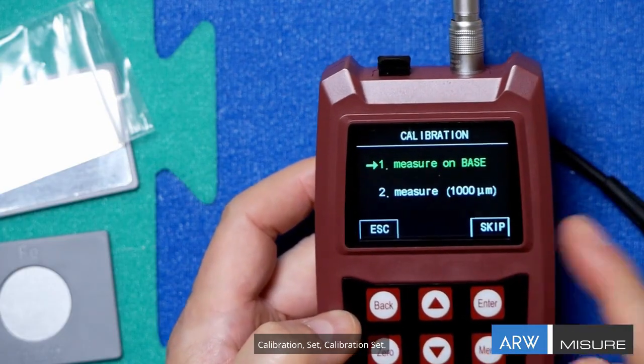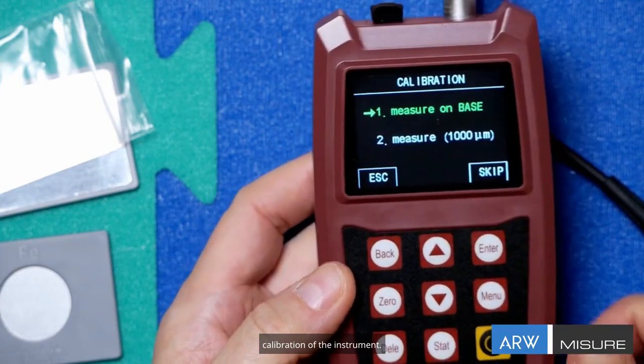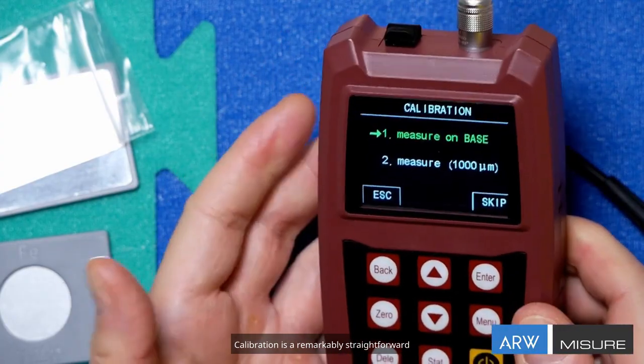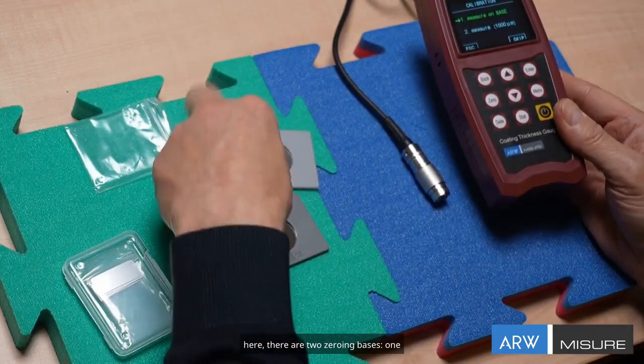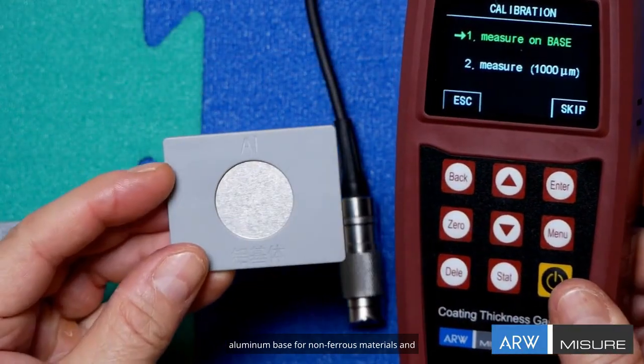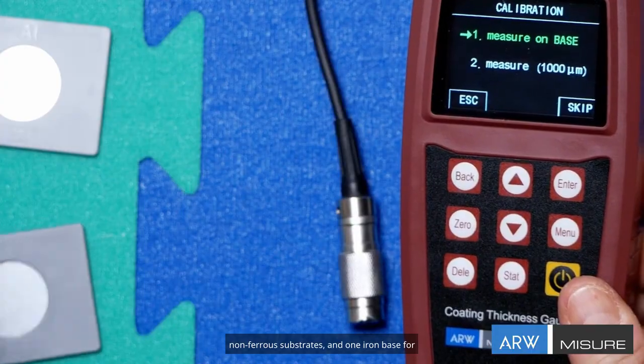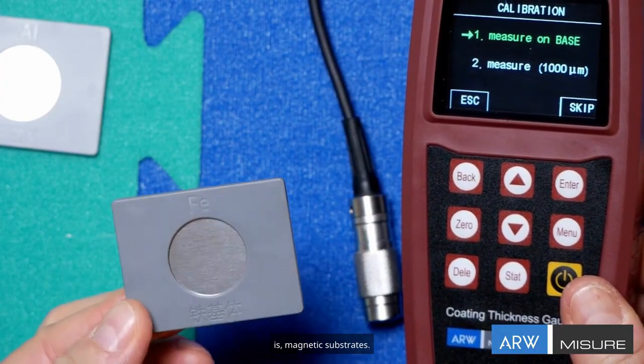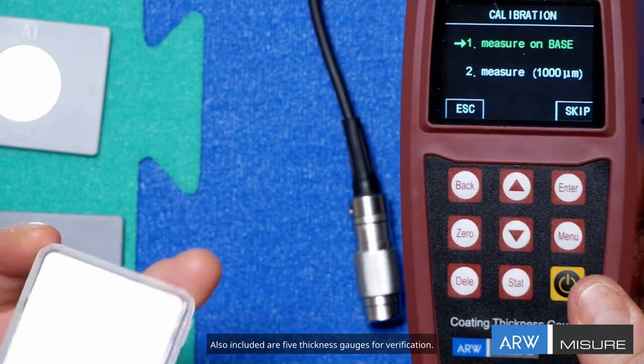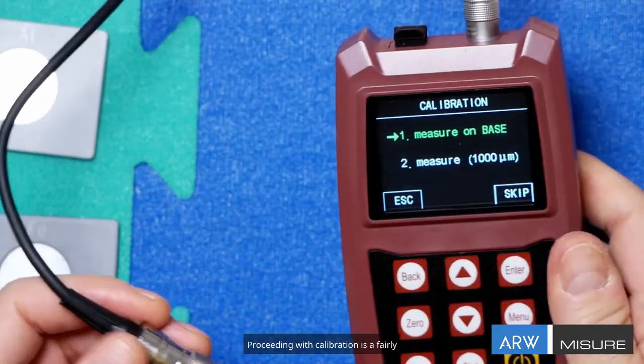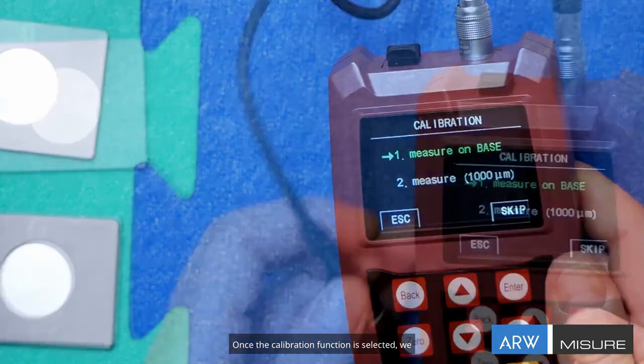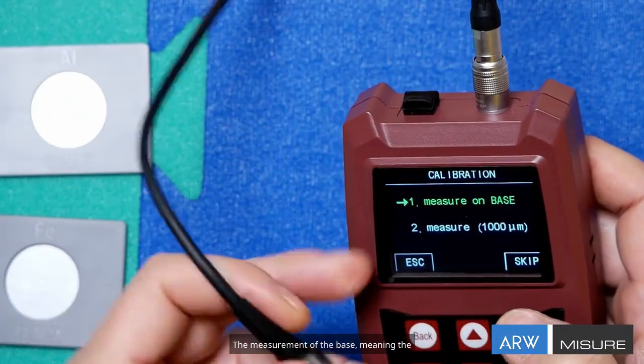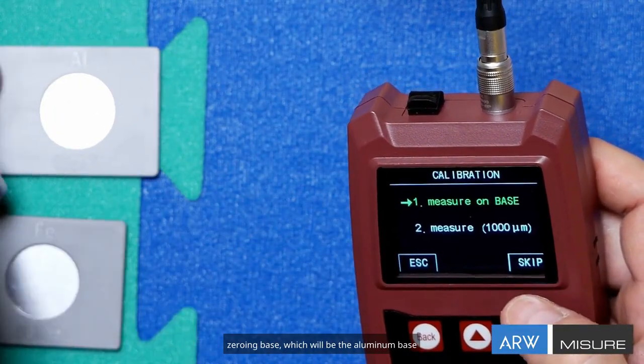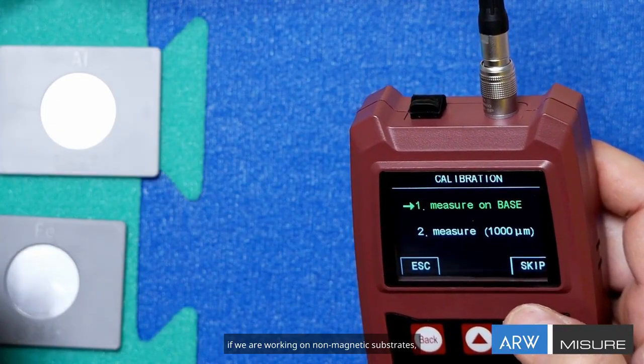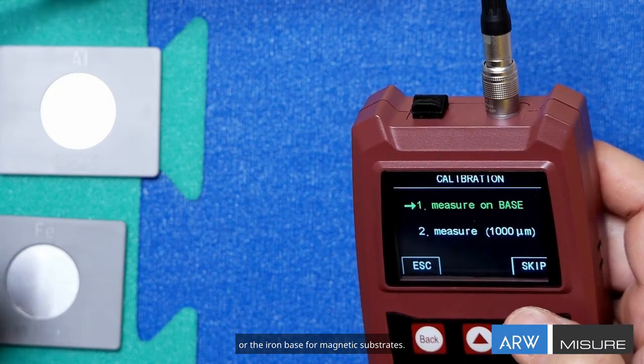Calibration set. This allows you to very easily perform the calibration of the instrument. Calibration is a remarkably straightforward and user-friendly procedure. Included in the kit, as we can see right here, there are 2 zeroing bases, one aluminum base for non-ferrous materials and non-ferrous substrates, and one iron base for magnetic and ferrous metallic materials, that is, magnetic substrates. Also included are 5 thickness gauges for verification. Proceeding with calibration is a fairly simple process. Once the calibration function is selected, we have 2 steps. The measurement of the base, meaning the zeroing base, which will be the aluminum base if we are working on non-magnetic substrates, or the iron base for magnetic substrates.